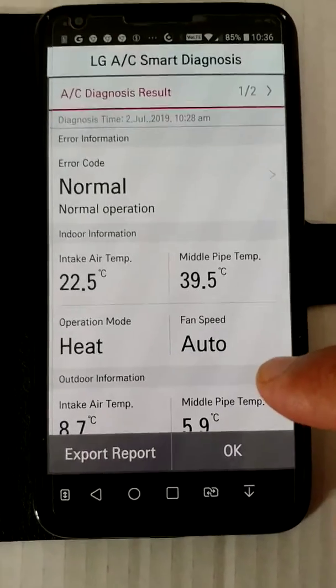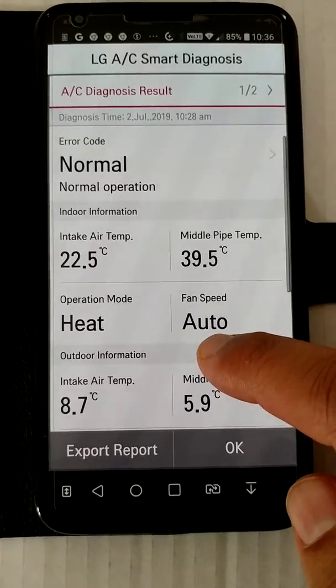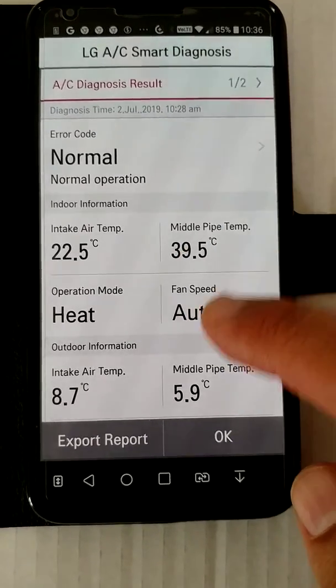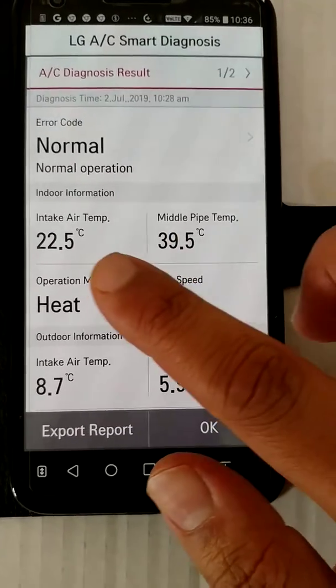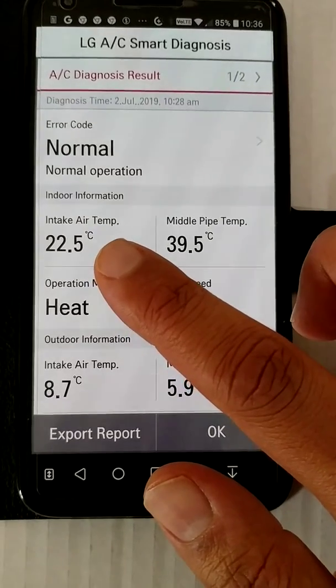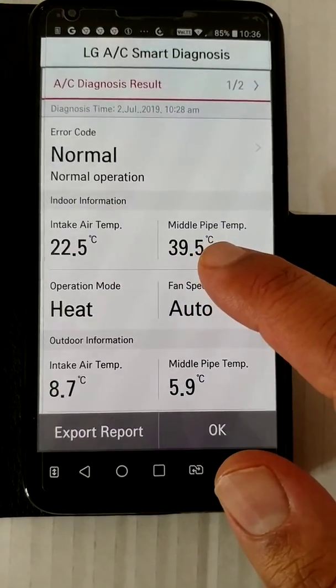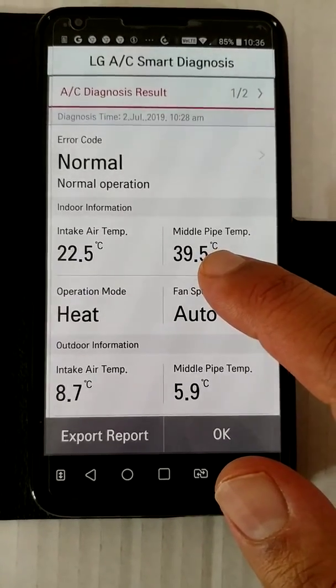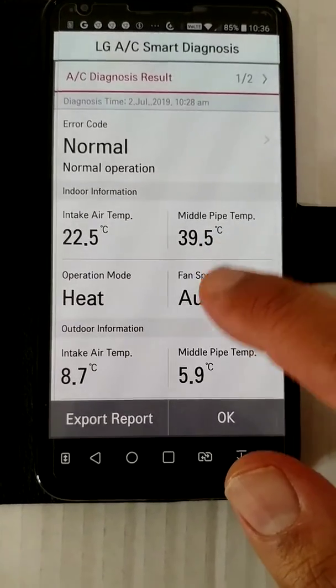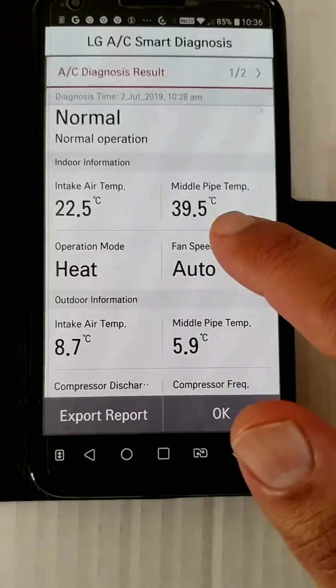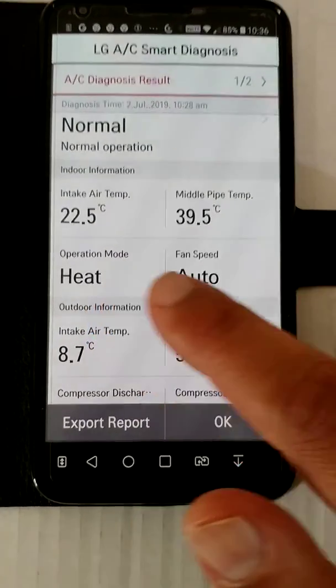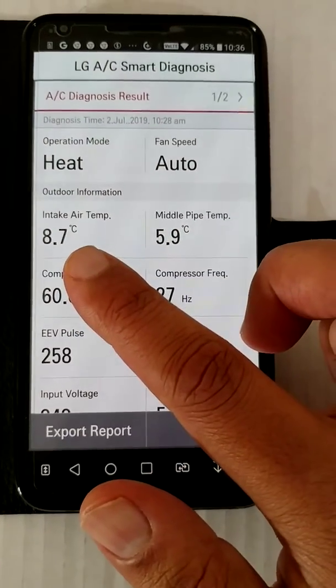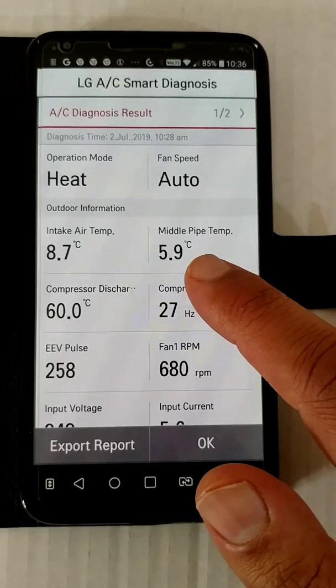Once you've downloaded the codes or the diagnostic status of the air conditioner: normal intake temperature is 22.5 degrees, the indoor evaporator is at 39 degrees. It's in heat mode, so the intake air is being heated by the coil at that temperature. Heat mode, auto fan speed, indoor-outdoor temperatures 8.7 degrees, and the middle pipe temperature of the condenser is 5.9 degrees.